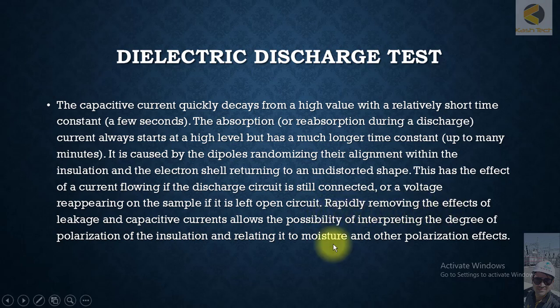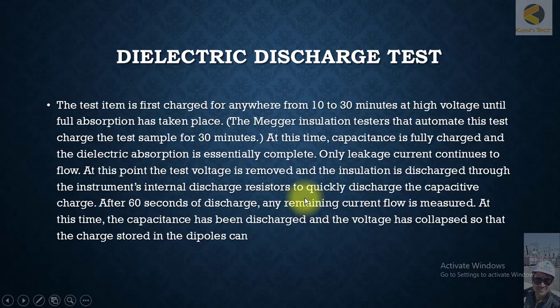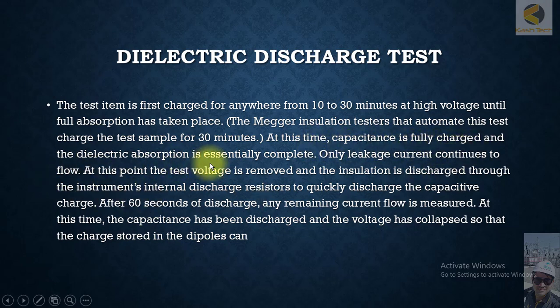Rapidly removing the effect of leakage and capacitive current allows the possibility of interpreting the degree of polarization of the insulation and relating it to moisture and other polarizing effects. The test item is first charged for anywhere from 10 to 30 minutes at high voltage until full absorption has taken place. The Megger insulation tester that automates this charges the test sample for 30 minutes. At this point, capacitance is fully charged and the dielectric absorption is essentially complete — only leakage current continues to flow.